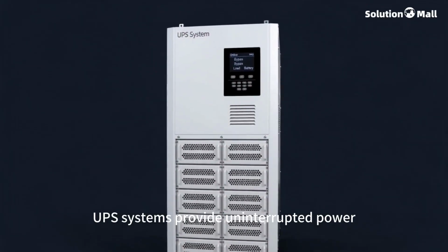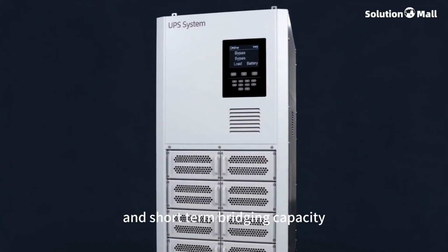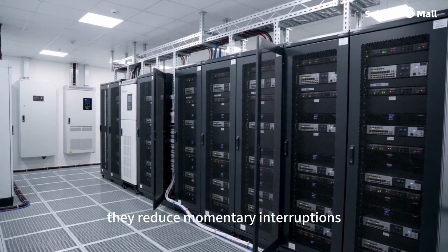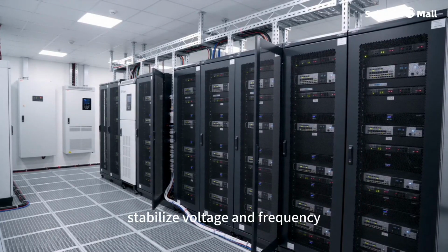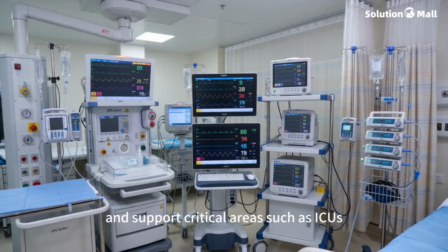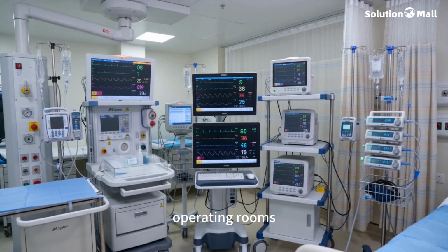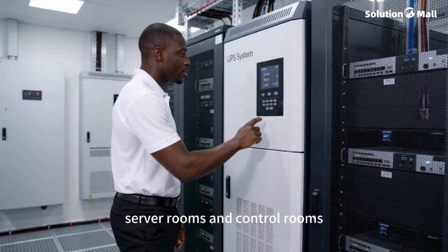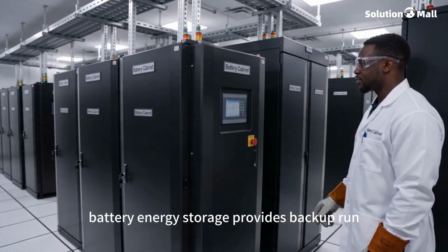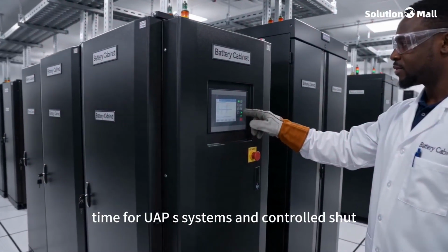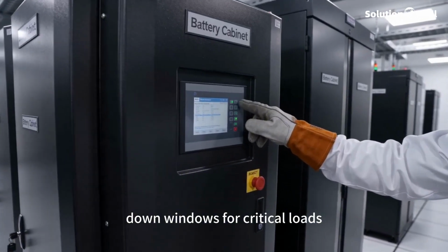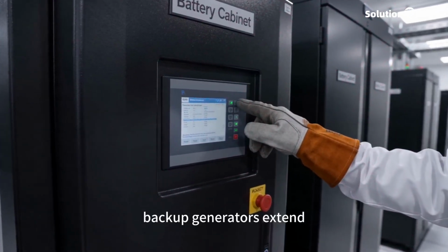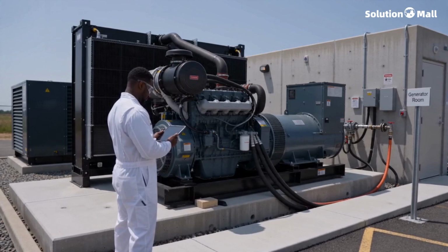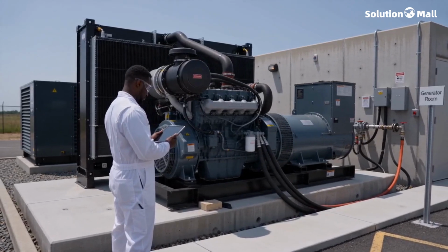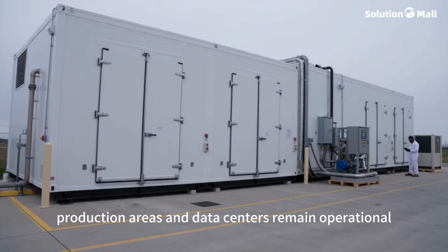UPS systems provide uninterrupted power and short-term bridging capacity. They reduce momentary interruptions, stabilize voltage and frequency, and support critical areas such as ICUs, operating rooms, laboratories, server rooms, and control rooms. Battery energy storage provides backup runtime for UPS systems and controlled shutdown windows for critical loads. Backup generators extend resilience during longer outages, helping hospitals, cold rooms, production areas, and data spaces remain operational.